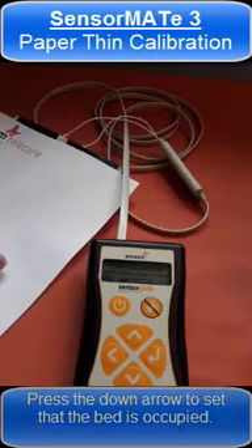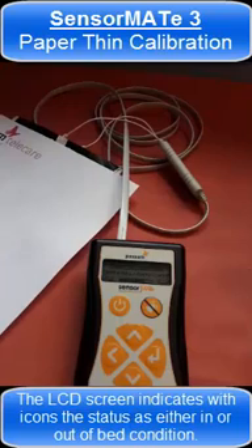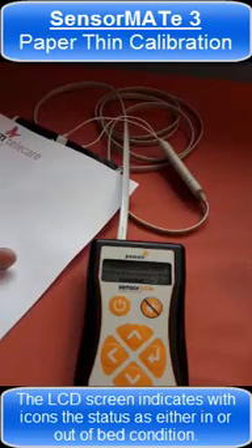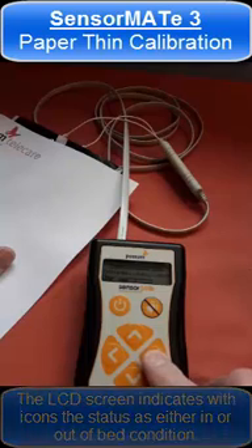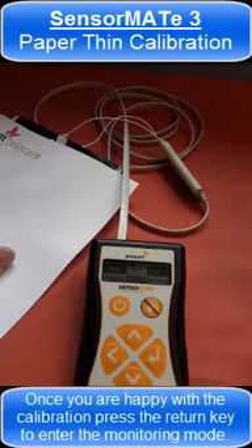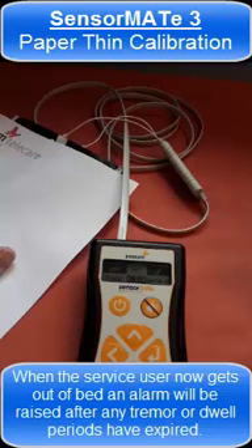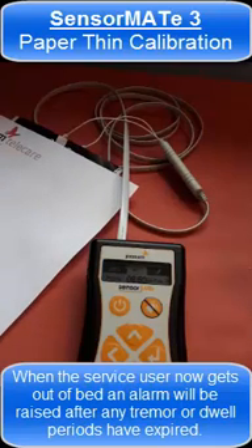Icons on the LCD screen will indicate whether or not there is an in-bed or out-of-bed condition. Once you are happy with the calibration, press the return key to enter the monitoring mode. When the service user now gets out of bed, an alarm will be raised after any tremor or dwell periods have expired.